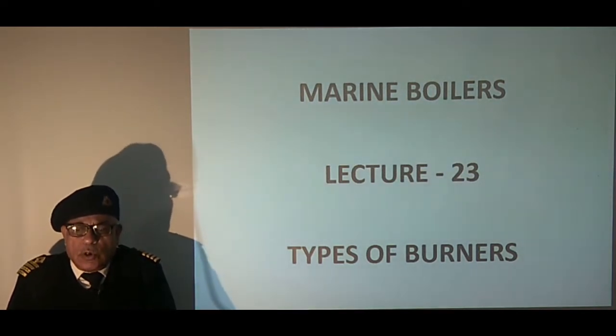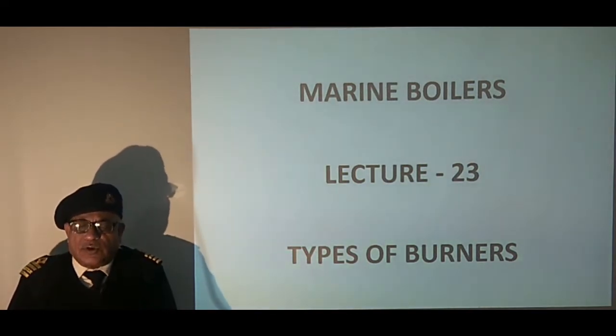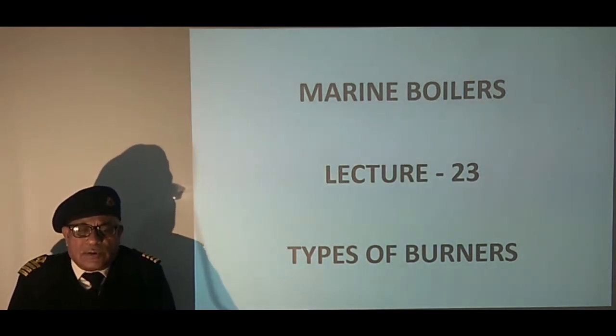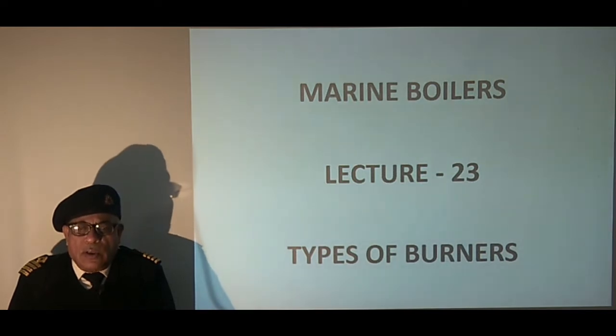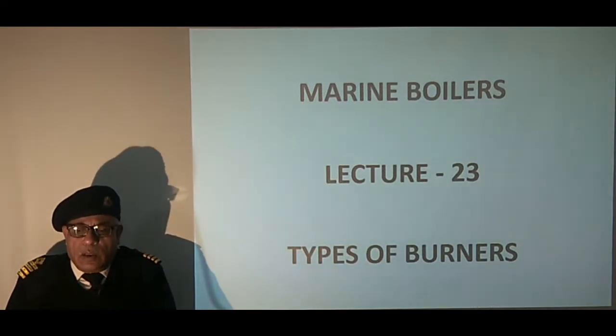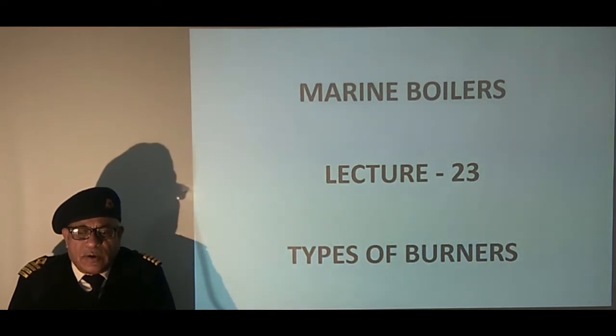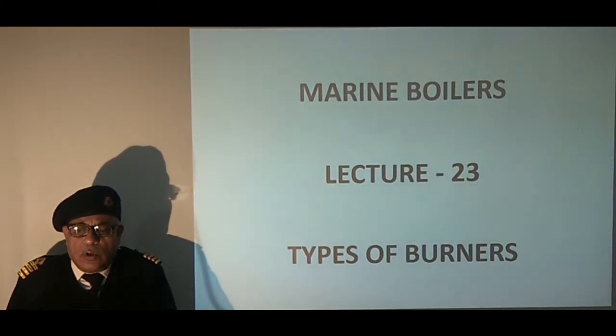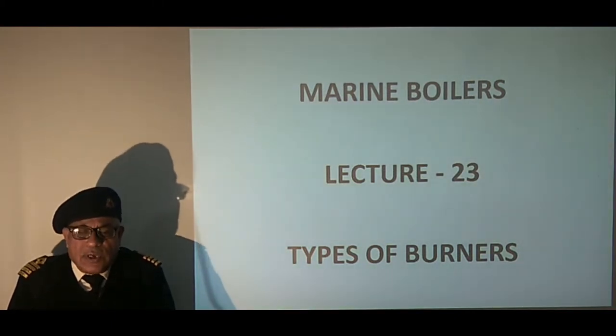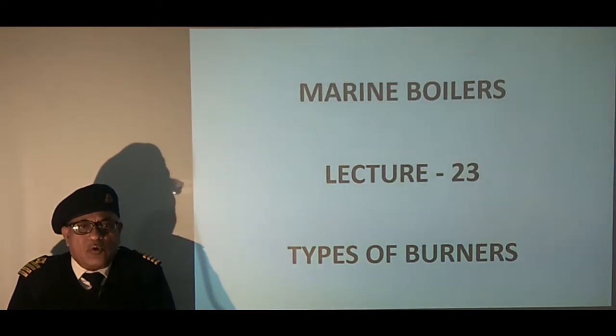Burners are used for atomizing the fuel for quick mixing with the surrounding air and causing efficient combustion. Oil fired boilers on motor vessels are used during port stay only and are required for small evaporation rate, for which pressure jet burner is quite suitable. On conventional oil tankers, boilers are used for moderate evaporation rate for which rotary cup, steam jet or ultrasonic burners are used. On steam ships, boilers are used continuously for large evaporation rate where dual fuel burners are used, which are explained in the following slides.